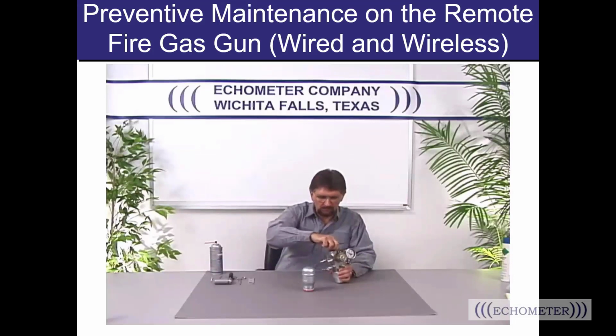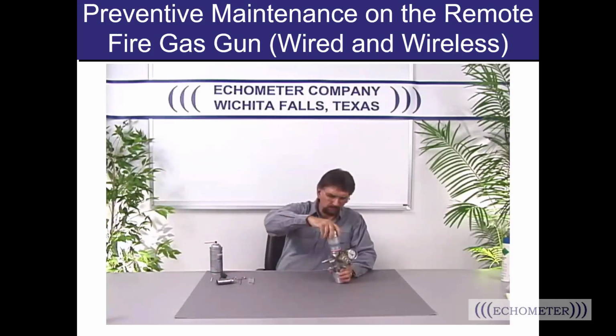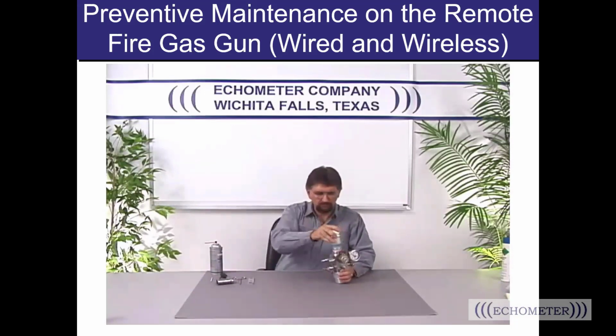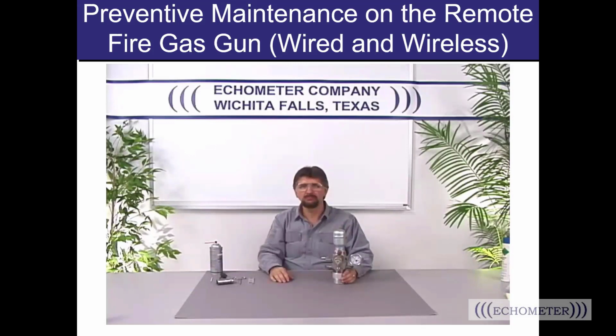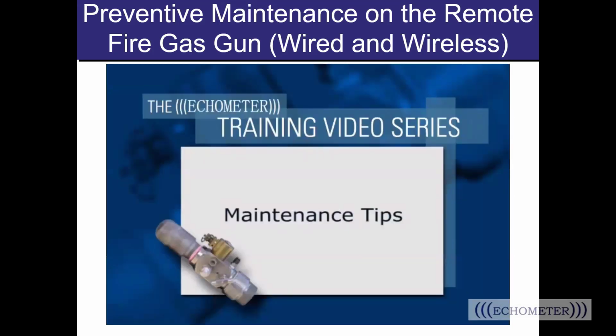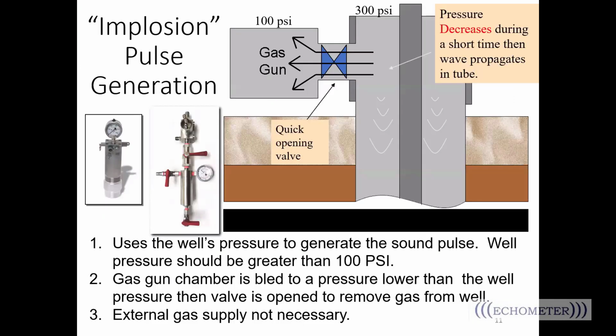All right, so you've checked your gas valve, the O-rings, make sure that it's lubricated, check your orifice and orifice housing, make sure that it's clear, make sure that it's clean, it's not damaged. You put all that back together, and then your volume chamber goes on top. So if you get stuck, you want to go in and see how everything was repaired, then you can always refer to that video there. All right.